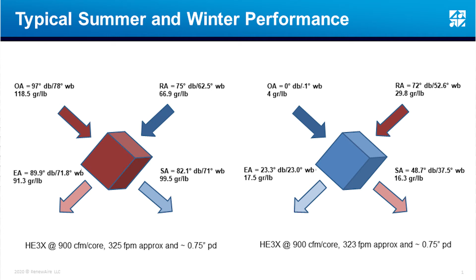The second thing that I would say is that very often you will see a design leaving condition from the DOAS unit of 55 degrees into the space. 55-degree dew point. The problem with that is that a 55-degree dew point into the space equates approximately to about 62 grains per pound in moisture. If you're looking to maintain the room condition set point at, say, 75 degrees and 50% relative humidity, that corresponds to a grain load of around about 67 grains per pound. So the difference between the grains of what you put in and what you're trying to control the space at, the return, is very small.